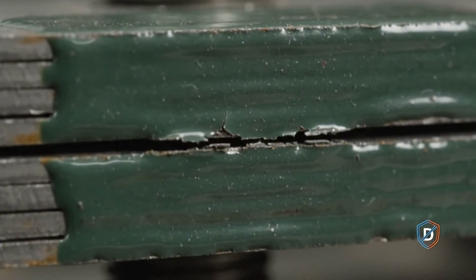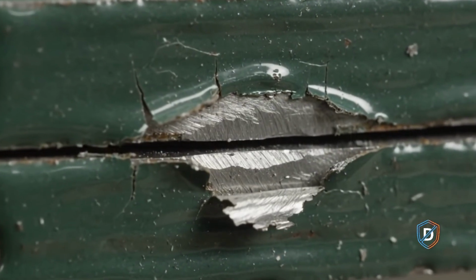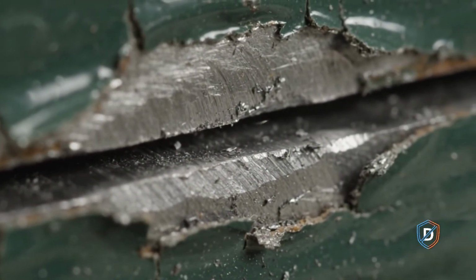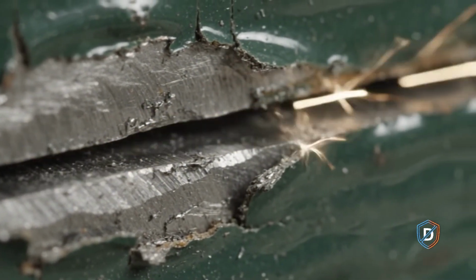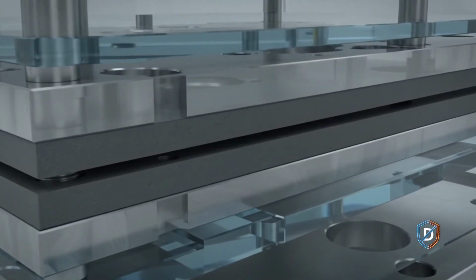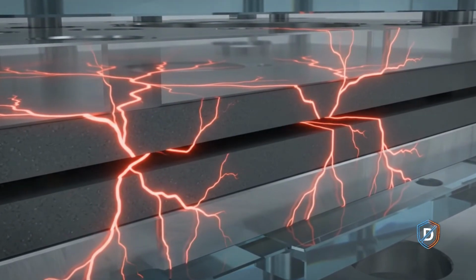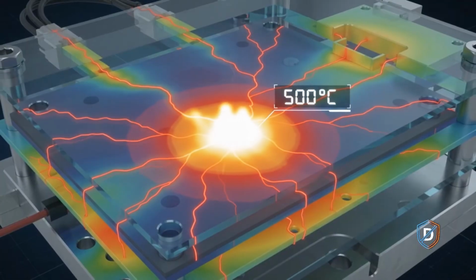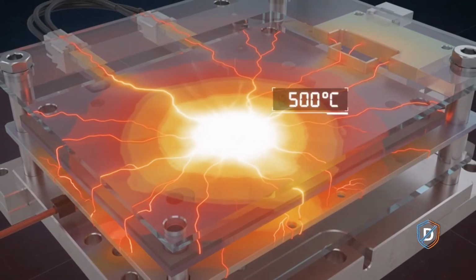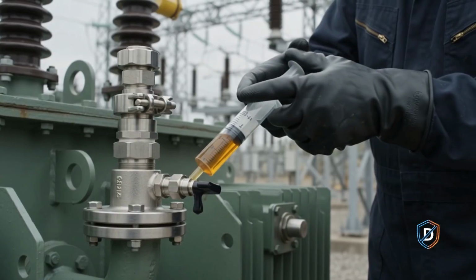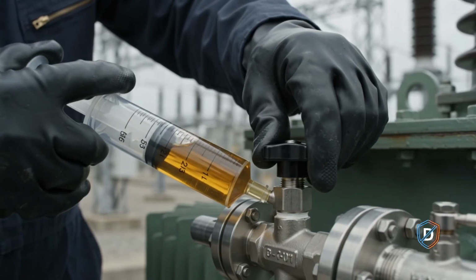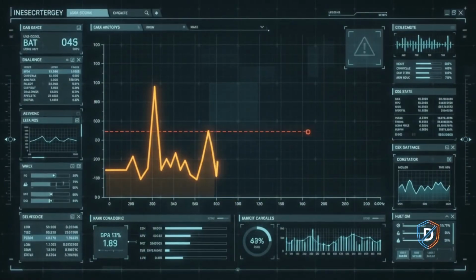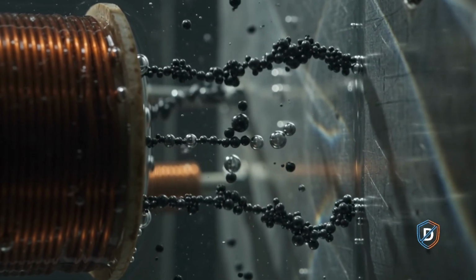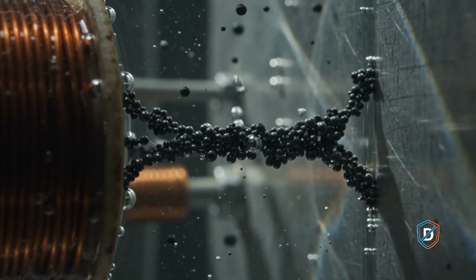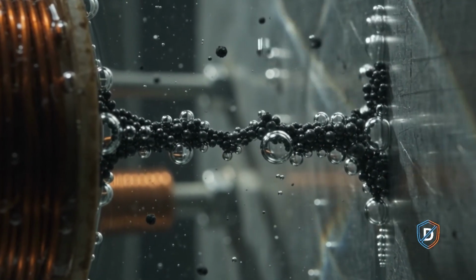Unclamped laminations rub together, scraping off varnish and creating direct metal-to-metal contact points. These microshorts allow stray current to jump across layers, creating localized hotspots exceeding 500 degrees. Grid operators extract oil samples monthly, using gas chromatography to detect early core breakdown before failure. When carbon buildup drops oil insulation strength below critical thresholds, a short circuit becomes inevitable.